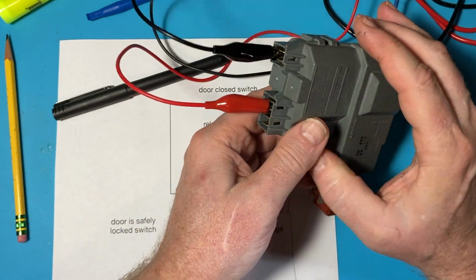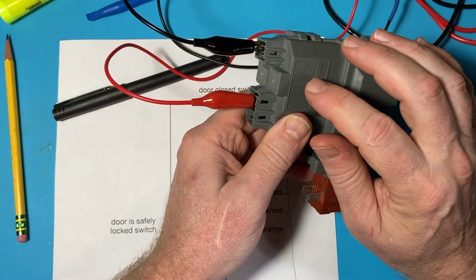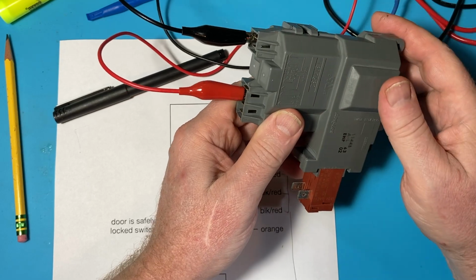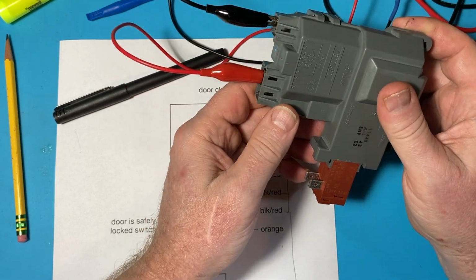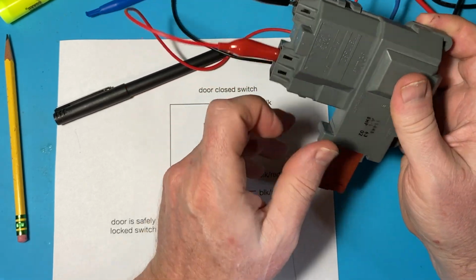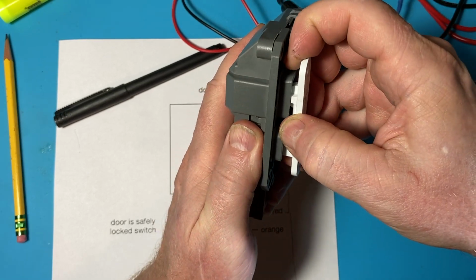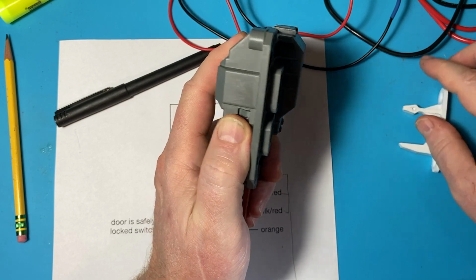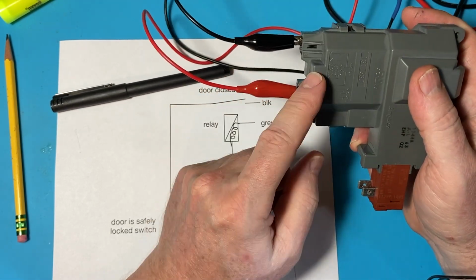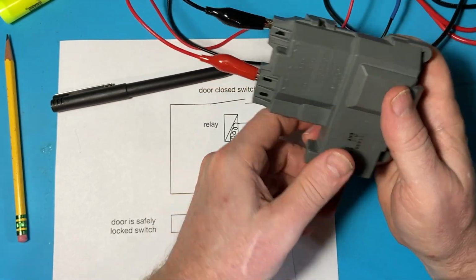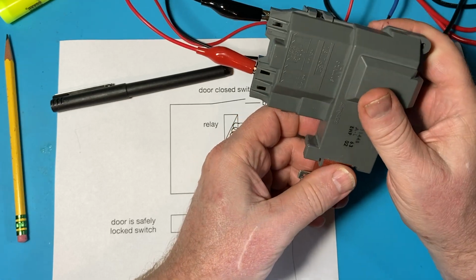But that would let you test the switch inside here without actually having to open this up. And of course, the other test you can do is to de-energize the relay, so you can pull this out, because when the relay is energized, this is locked in. So you pull that out, and then energize the relay, and this should not beep because the door is not in.